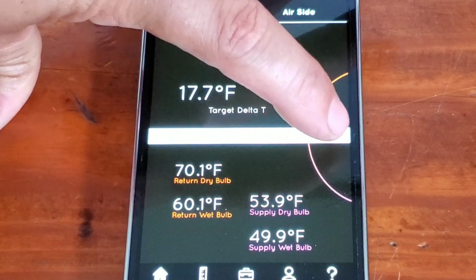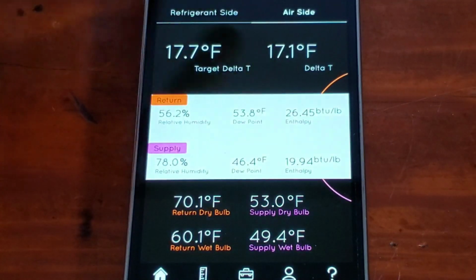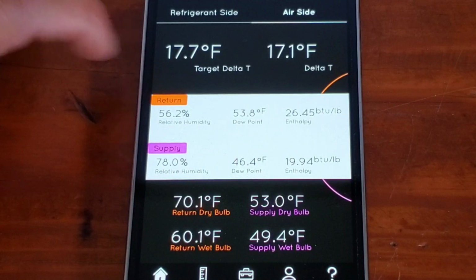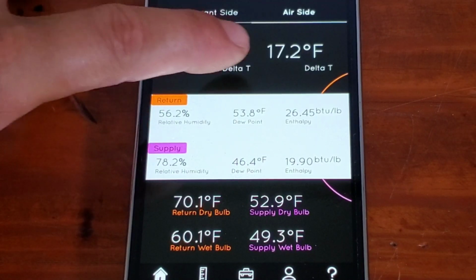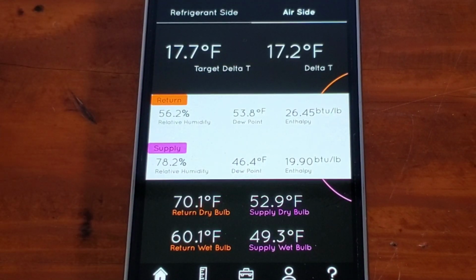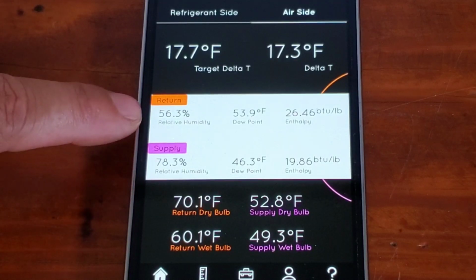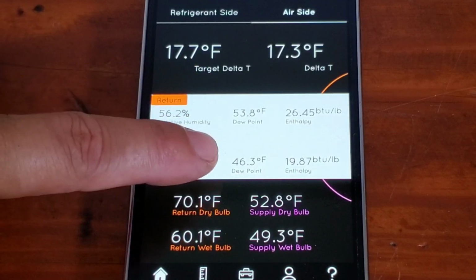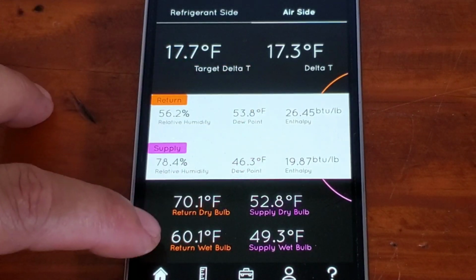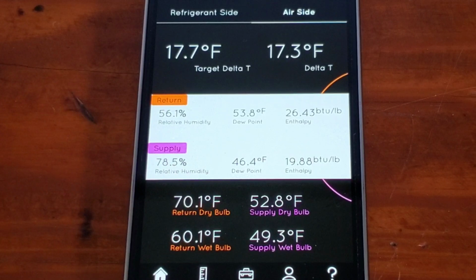Again, super easy to navigate the menu. Go over to the air side, click the little plus button so we get all our information. You can see our target delta T is 17.7, actual 17.2, so we're right in there. It also gives you your relative humidities, return and supply, your dew points, your enthalpy, and then down below your wet bulb and dry bulb, return and supply.